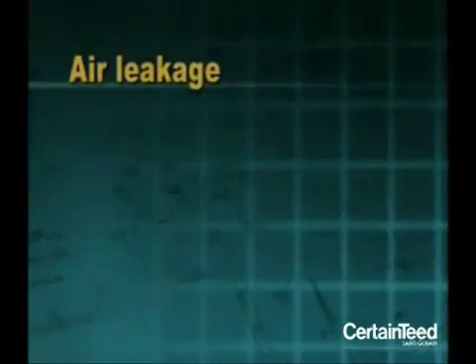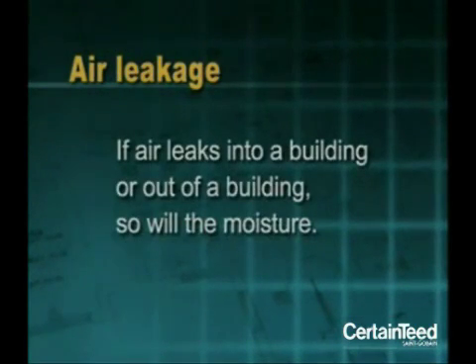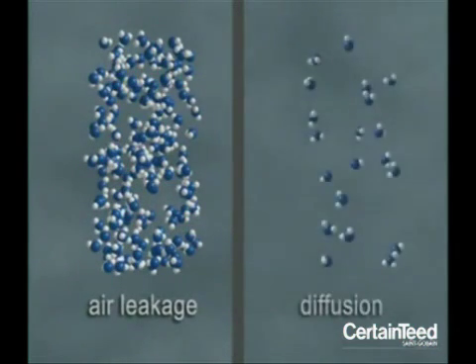Another way airborne moisture moves through a building is as the result of air leakage. Since the moisture is in vapor form and mixed in with the air, if air leaks into a building or out of a building, so will the moisture. Moisture carried in or out of a building due to air leakage can be 10 times to 100 times greater than moisture transferred by diffusion.